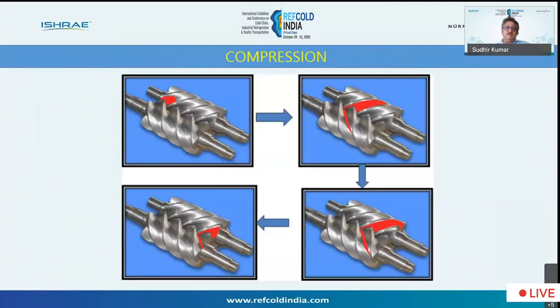So the major advantage of a screw compressor is you save on the plant room space, plus the automation of the controls, and the capacity control mechanism is very good in a screw compressor, where you can operate it at 10% also. And also you can use a VFD drive. Of course, there will be a slight power penalty if you are using capacity control and running a plant at 50%. Definitely there will be a power penalty. So the system must be optimally designed in such a way that you have multiple compressors based on your capacity. So once you select your compressor, the energy saving happens in the compressor part.